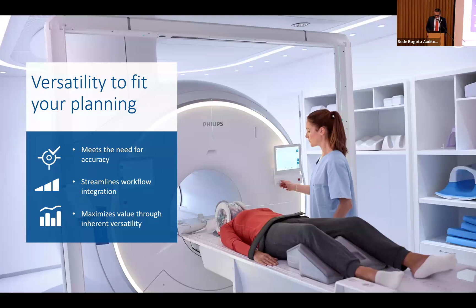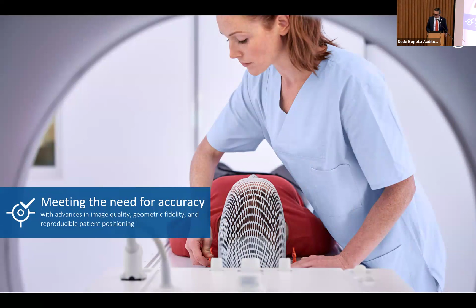But there are systems, MRI systems, that have developed new solutions in order to get planning with not a standard, but a regular MR. For instance, we can use, in this case, a laser structure for isocenter. So that now is possible. We can use the same devices or very similar devices as the fixed devices that are used for CT that are available for MR. The other important thing is the bore size.